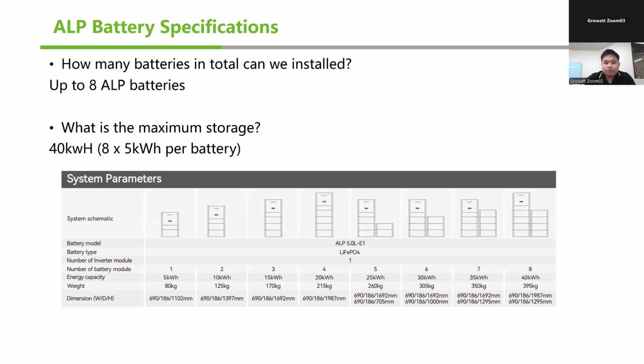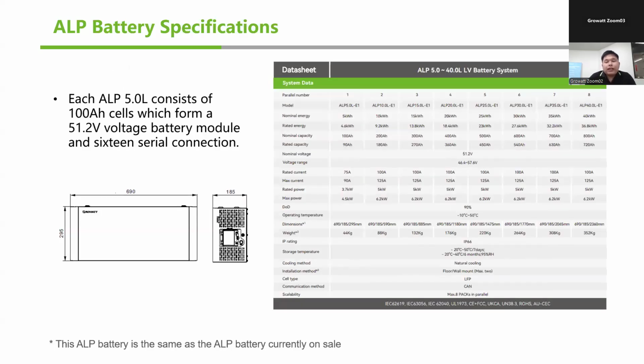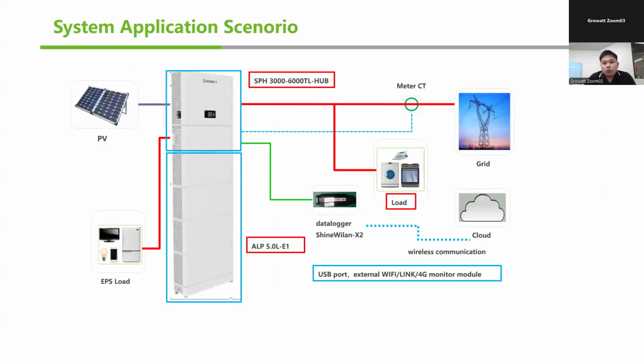Each ALP 5L battery, where the L stands for low voltage, consists of 100 ampere-hour cells, which form around 51.2 volts per battery module with 16 serial connections. The dimensions for the batteries are roughly 295 millimeters in height and 690 millimeters in width. So the system application scenario here is if only one system is installed.